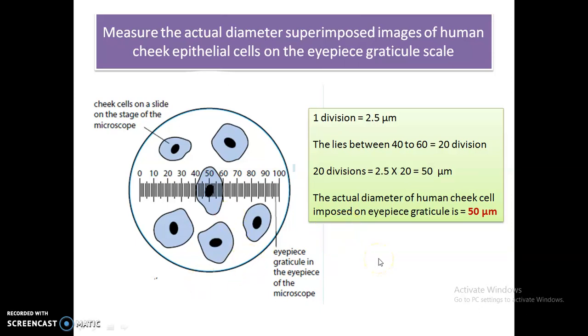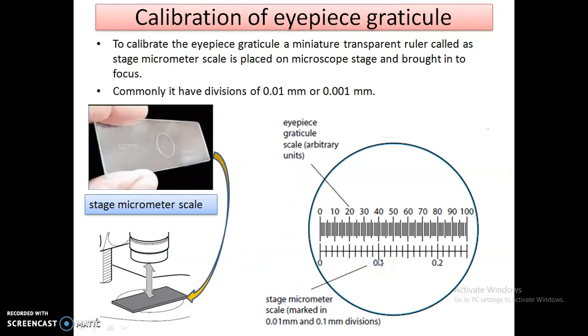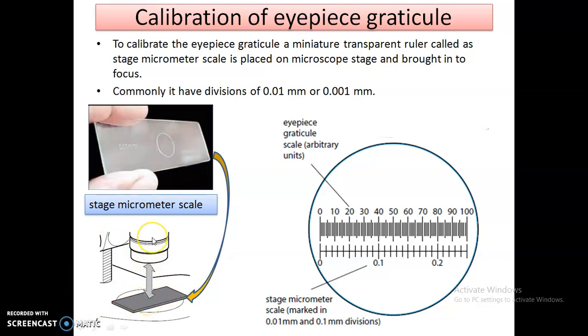Now, how do we calibrate the eyepiece graticule? Calibration is done with the help of a stage micrometer scale. This stage micrometer is a miniature transparent ruler which is placed on the stage of the microscope. At whatever magnification we want to observe, we adjust this stage micrometer at the same magnification and view it through the eyepiece lens.